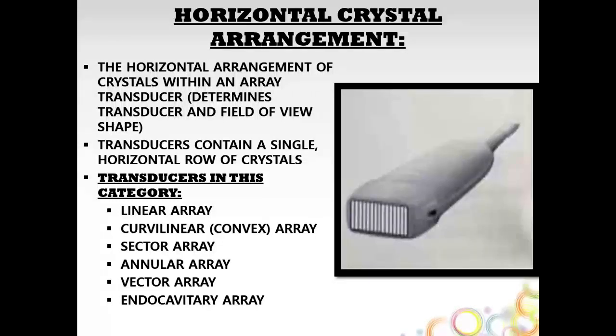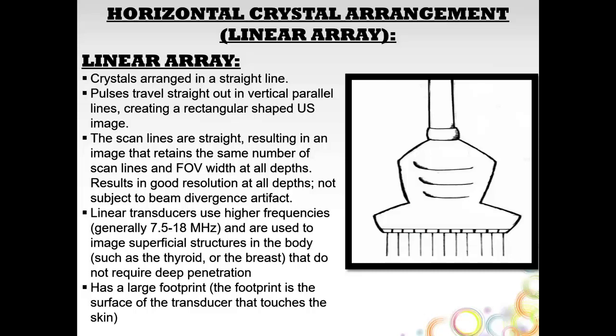So first, our horizontal crystal arrangement. This is where, again, we just have one row of crystals. They can be arranged in various shapes. And this determines what our field of view is. Our field of view is basically our ultrasound image shape. So there's many transducers in this category: linear arrays, convex arrays, sector arrays, annular arrays, vector arrays, and endocavitary arrays. So this is our bread and butter transducer, our linear array. This is what we use in breast imaging.